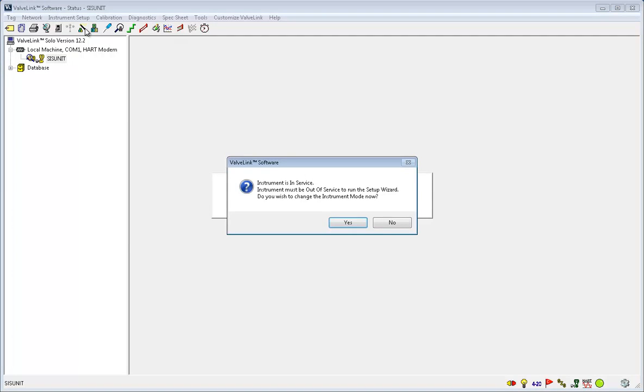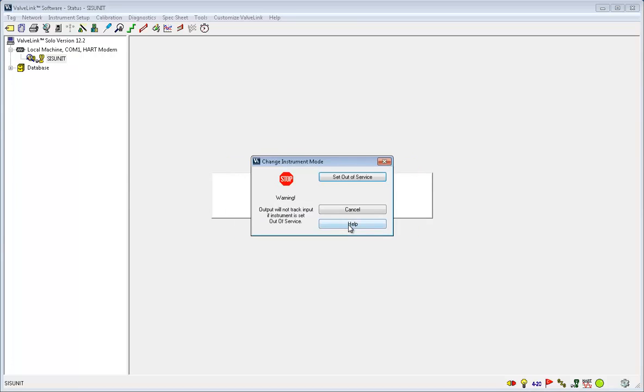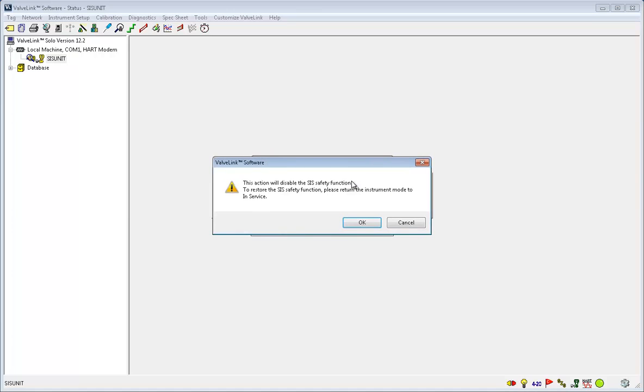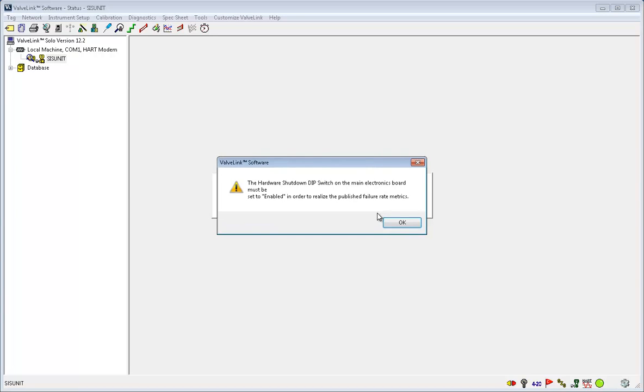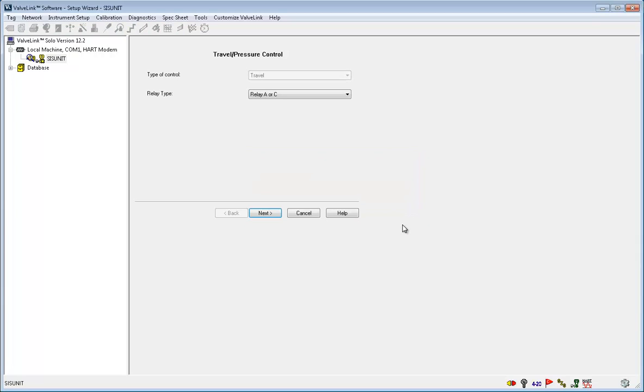First, we are going to take the instrument out of service. Click Yes, and then click Set Out of Service. Note that if the DVC6200SIS is set with the hardware shutdown circuitry enabled, the device will still respond to changes in signal and the valve will move. So click OK, and now the setup window will open.